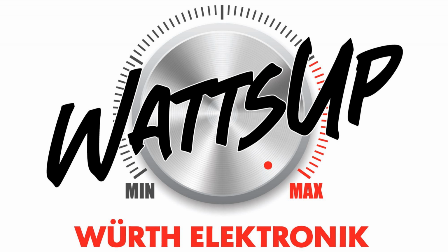Related to the leakage inductance is the winding structure. In principle, there are different types of winding structures possible. On the left side, we see the so-called sectional winding, where we have a separation of the windings on the core. So it's a geometrical or spatial separation, and mostly also with a separator between the windings just to increase the creepage and clearance distances.